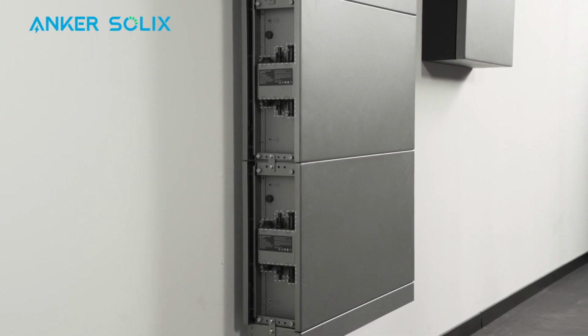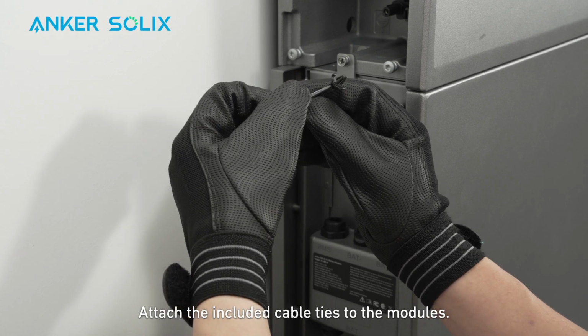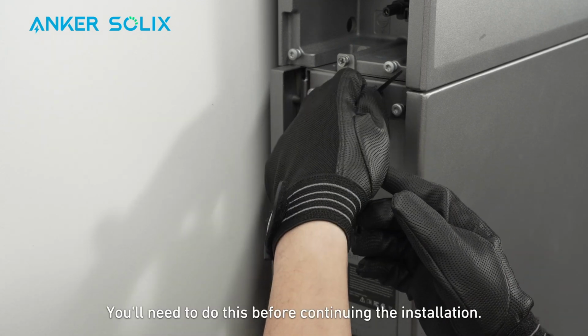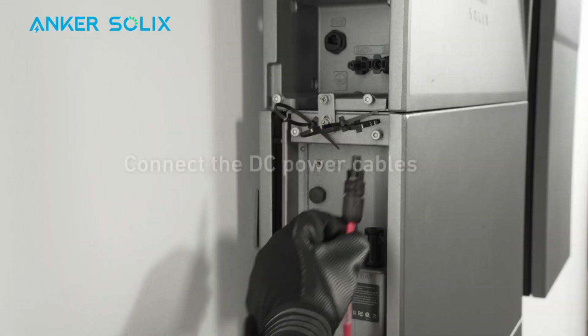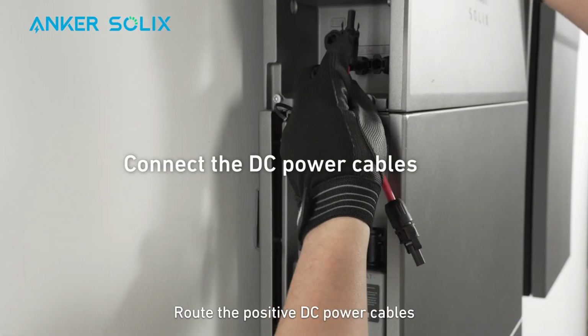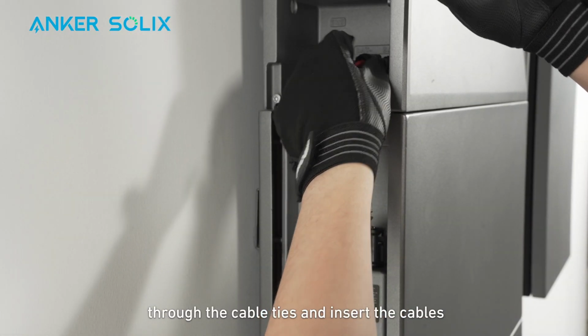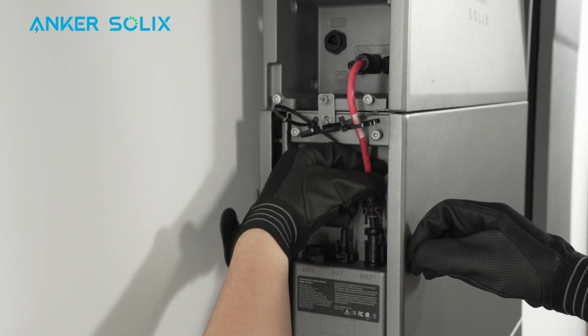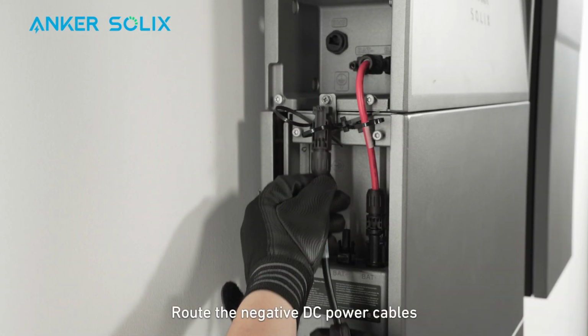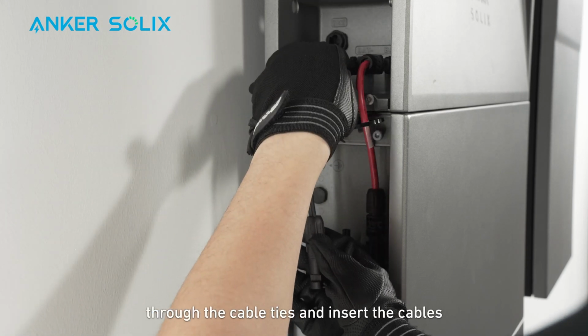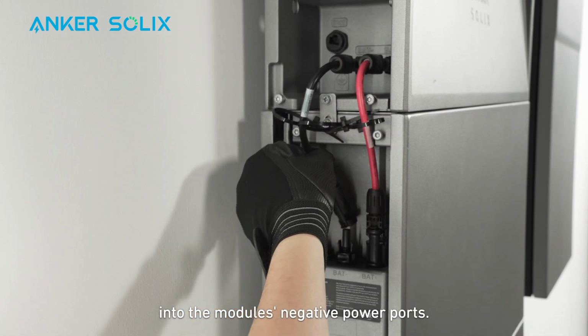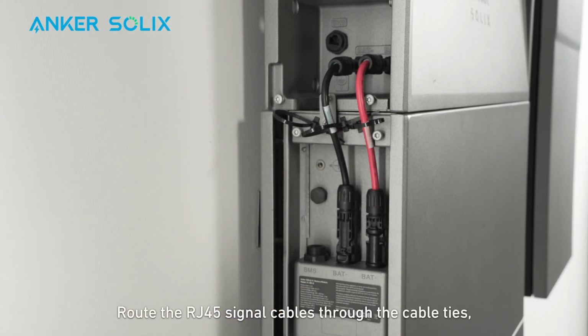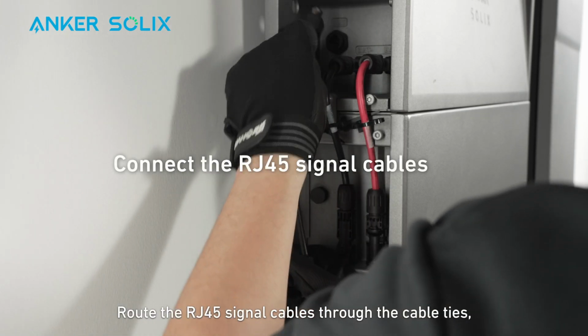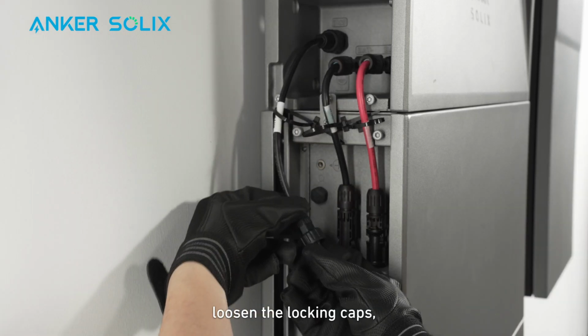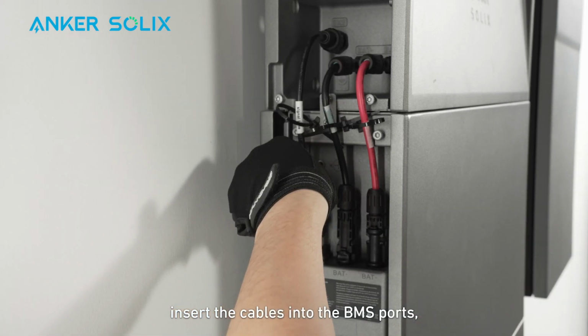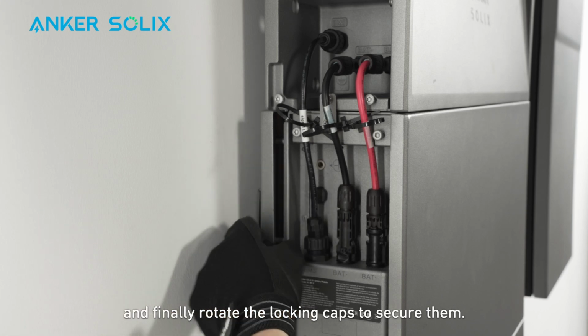Attach the included cable ties to the modules. You'll need to do this before continuing the installation. Route the positive DC power cables through the cable ties and insert the cables into the module's positive power ports. Route the negative DC power cables through the cable ties and insert the cables into the module's negative power ports. Route the RJ45 signal cables through the cable ties. Loosen the locking caps, insert the cables into the BMS ports, and finally rotate the locking caps to secure them.